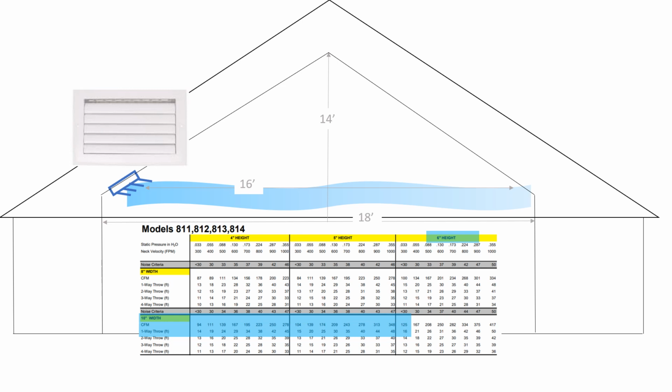overlooked. Now, I think this has to be done before the ducts are sized, since the register throw dictates the register placement, which is what you need to finalize before you can figure out what your total effective length is. You can't size ducts before you do any of this, so it often gets overlooked, but it shouldn't. Now I had everything I needed to design my duct system.